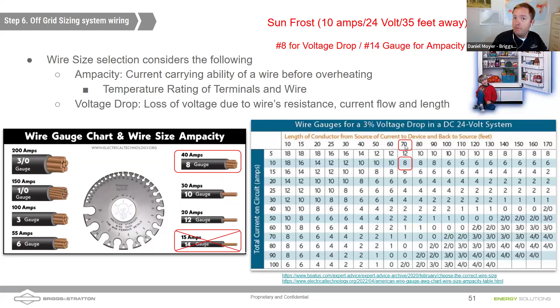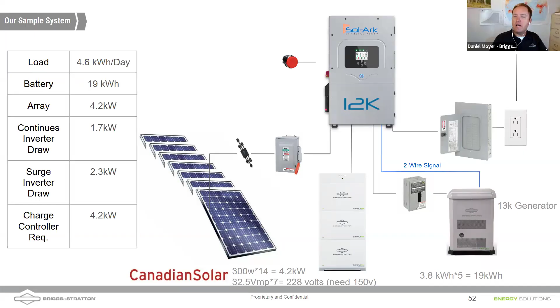Here's our system: 4.6 kilowatt hours is our load. We're going to have a 20 kilowatt hour battery, 4,000 watts of solar. You might not get exactly there because panels don't always come in the increments that you want. And we've got an inverter, and I'll go ahead and slap in a 13K generator as well.